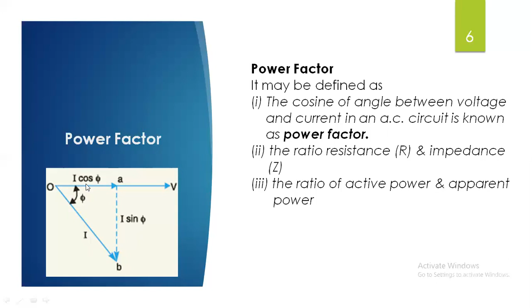Let's see the power triangle. From the power triangle, we can calculate the power factor. How is it calculated? This power triangle has active power VI cos phi, reactive power VI sin phi, and apparent power V into I. As per the Pythagoras theorem, OB square is equal to OA square plus AB square. So apparent power square is equal to active power square plus reactive power square, that is kVA square is equal to kW square plus kVAR square.